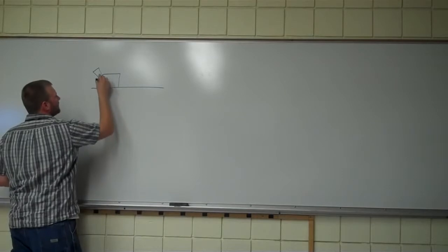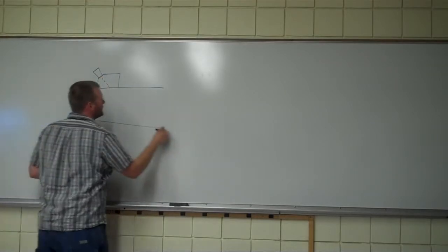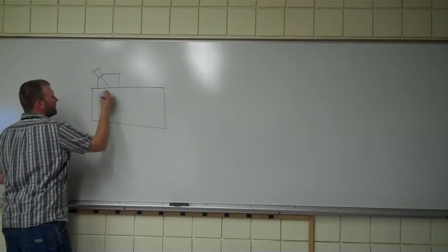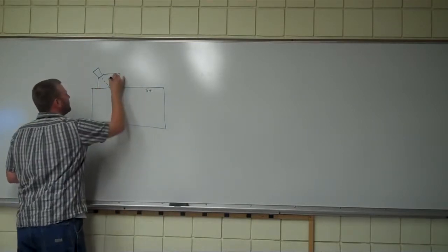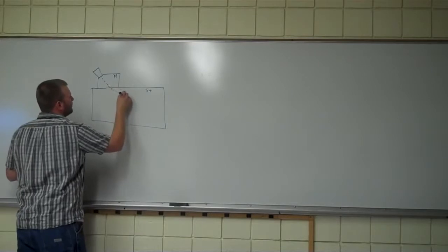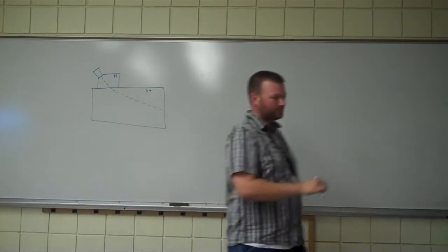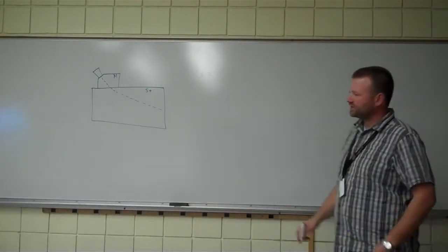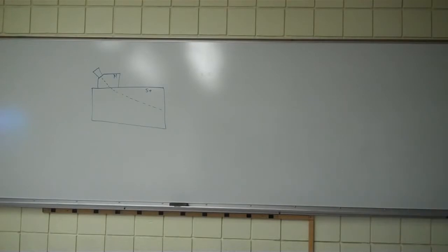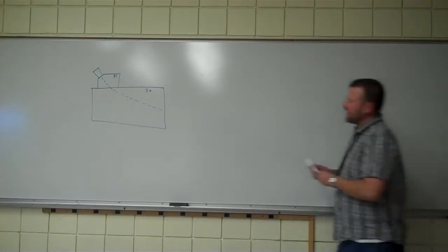That's going to tell us, if we have one material, in this instance steel, and another, plexiglass, what angle the sound beam coming out of the transducer is at. Nothing terribly difficult, just trying to make sure we can figure all that out, because we want to see these defects as close and as accurately as we can on these screens. Next week we'll start getting into screens and what they actually look like.